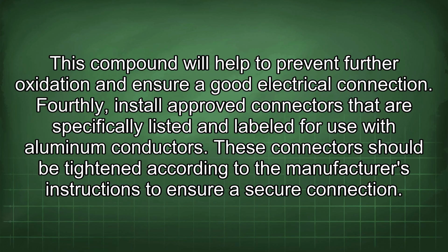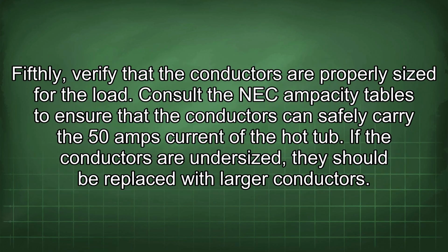Fourthly, install approved connectors that are specifically listed and labeled for use with aluminum conductors. These connectors should be tightened according to the manufacturer's instructions to ensure a secure connection. Fifthly, verify that the conductors are properly sized for the load. Consult the NEC ampacity tables to ensure that the conductors can safely carry the 50 amps current of the hot tub. If the conductors are undersized, they should be replaced with larger conductors.